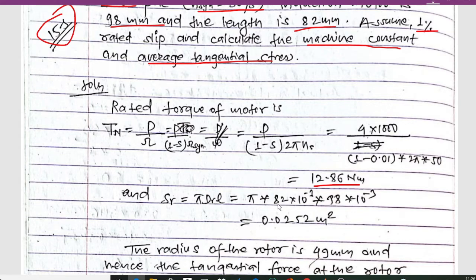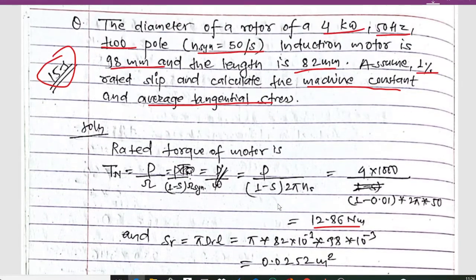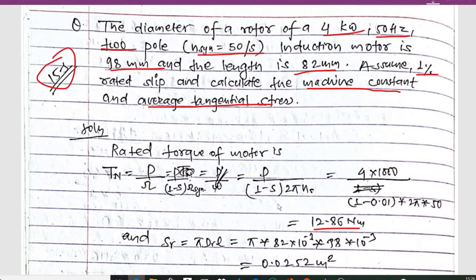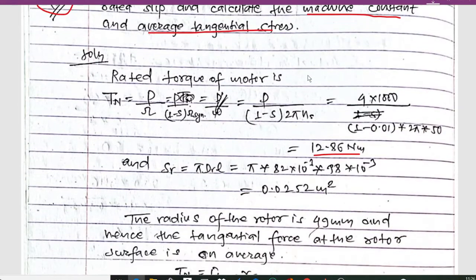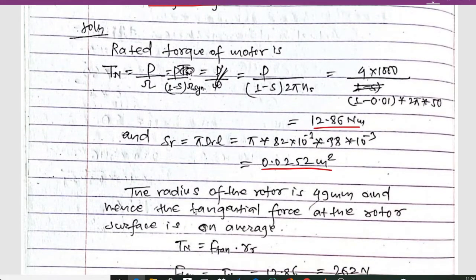The rotor surface area is calculated as Sr = π · D · L. Here the diameter D is 98 mm and the length L is 82 mm. So Sr = π × 82 × 10⁻³ × 98 × 10⁻³ = 0.0252 m².